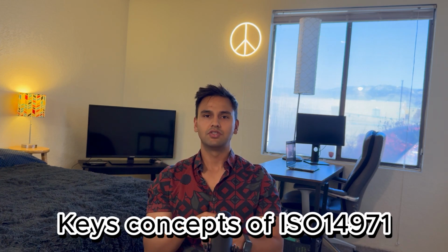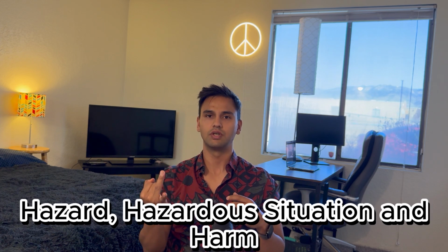Now let's talk about the key concepts. There are some key concepts that you need to know and be familiar with to be successful in risk management. There are tons of them listed directly in the ISO standard, but in today's lecture we'll be talking about three major key concepts, right? Those key concepts would be hazard, hazardous situation, and harm, right? If you learn these three, you'll be using them in all your documents such as PFMEA and DFMEA, so you'll be really good on that. So what is a hazard, you may ask? A hazard is anything that could potentially cause harm to your patient, right?